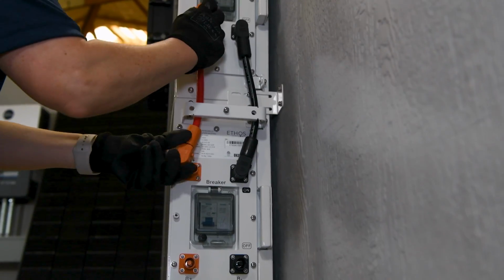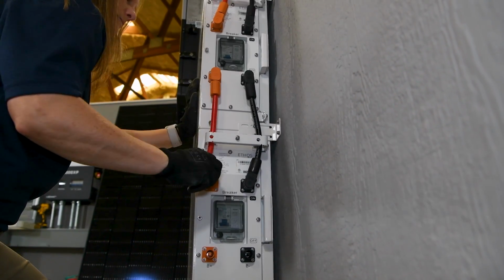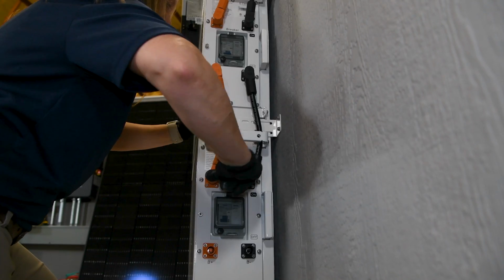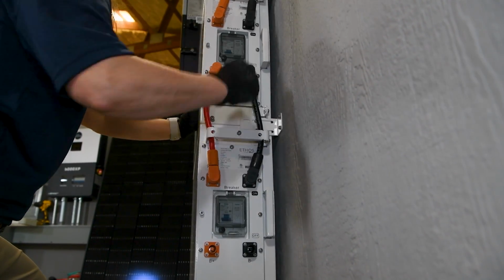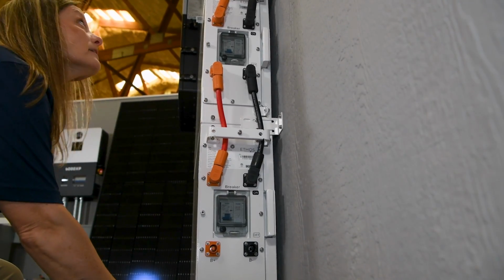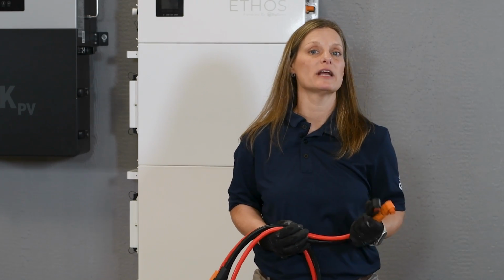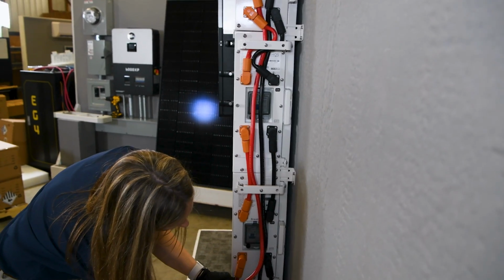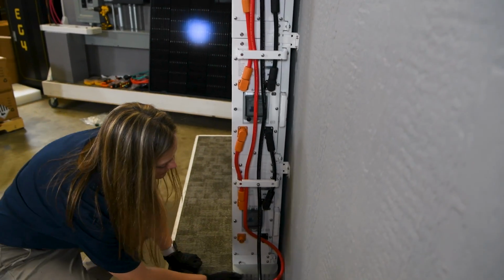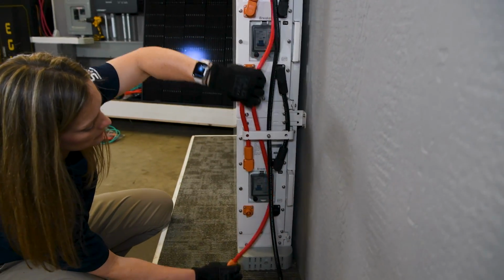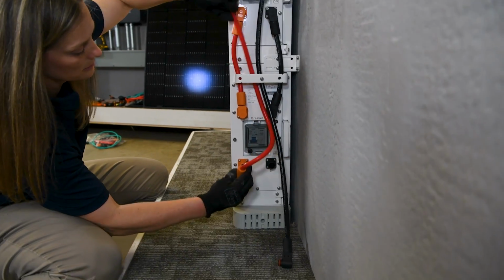Continue this process, connecting from one battery module to the next down to the bottom of the stack. Upon reaching the bottom, we'll explore some alternative configuration options. When you reach the bottom battery module, it's crucial to ensure the efficient distribution of the 200 amp current.